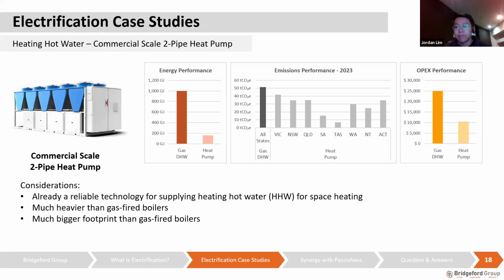So here are the metrics of a commercial scale 2-pipe heat pump. Similarly, it's about more than 80% reduction in energy, and it's a measure that can be applied by all states here. You can see here that heat pump technology in a typical scenario can operate with lower emissions compared to, well, it seems to be a typo here, it should be a gas boiler instead of a gas domestic hot water system, but you probably get the gist.